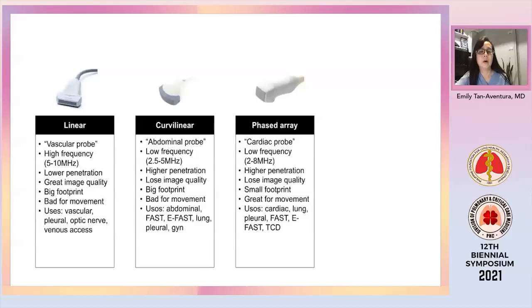The linear probe, also called the vascular probe, has the highest frequency among the three. However, it has the lowest penetration. Hence, it's used mainly for superficial structures like blood vessels and the pleura. The curvilinear and the phased array probes have lower frequency, but they do have higher penetration. So you can evaluate deeper structures with these two probes. The difference between the two is that the curvilinear probe has a bigger footprint and the phased array probe has a smaller footprint. Both can be used to evaluate the lung and the pleura.